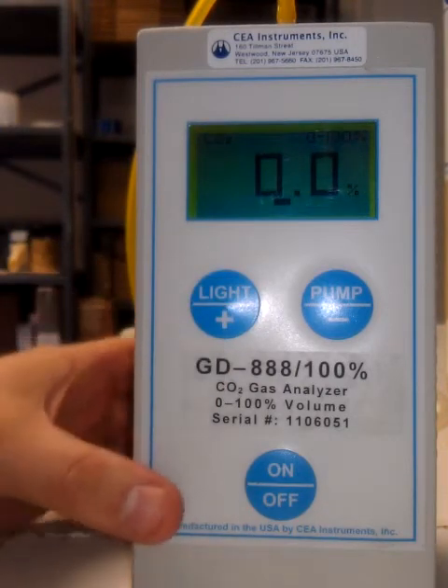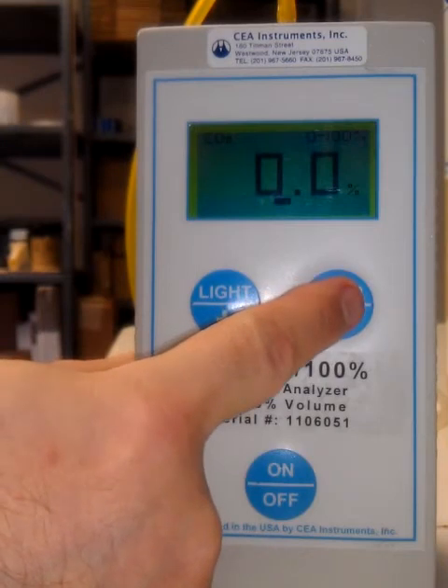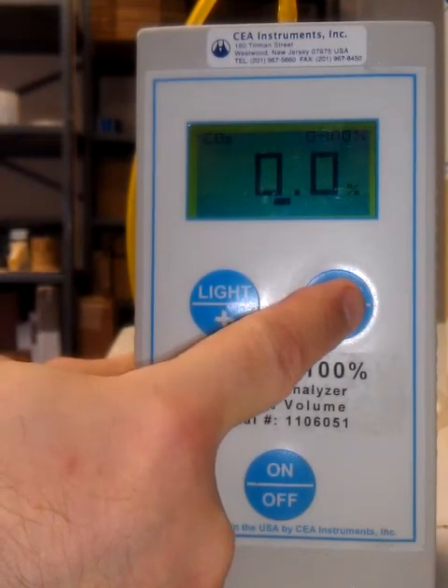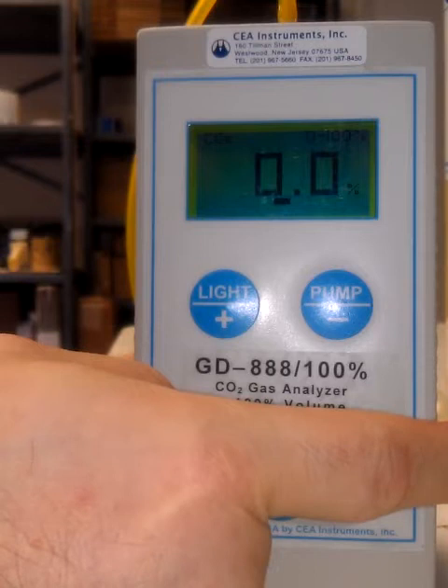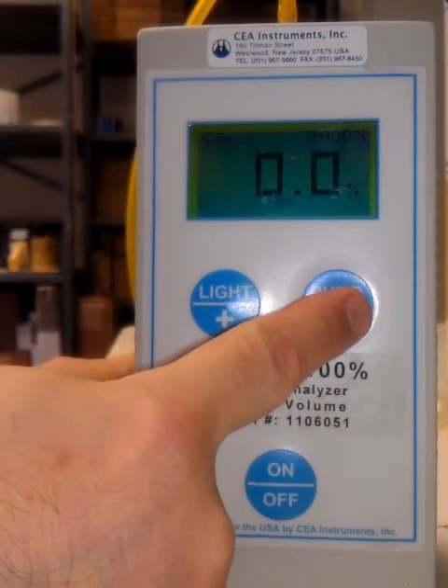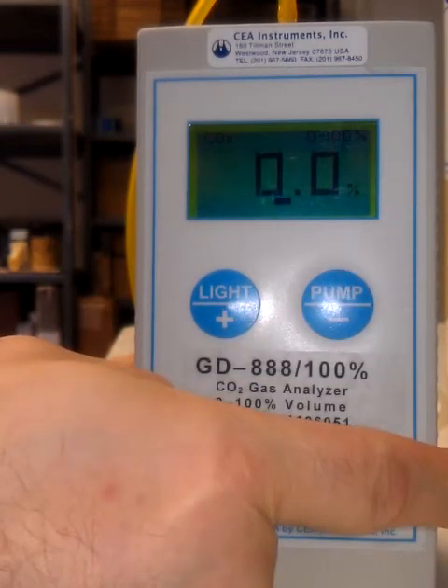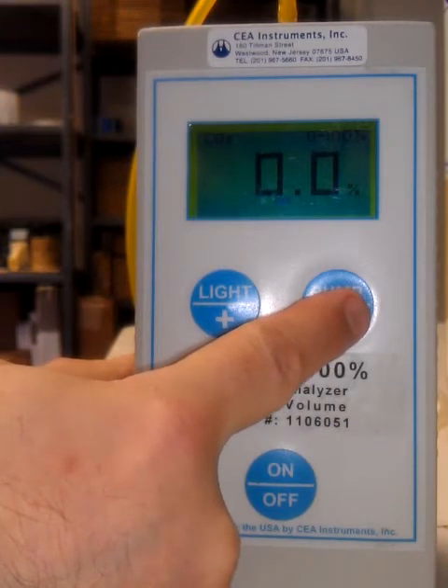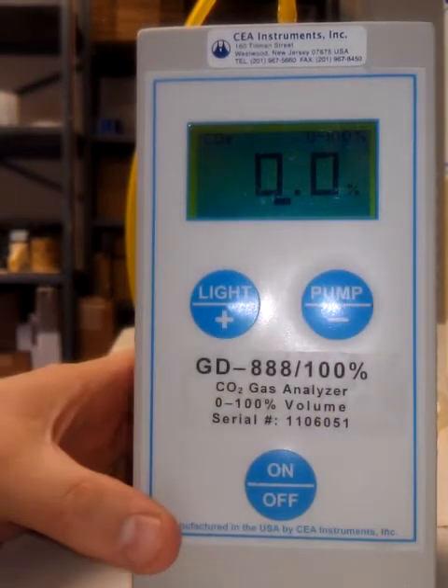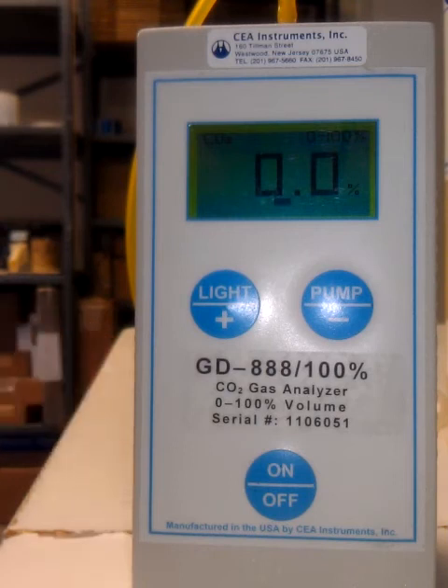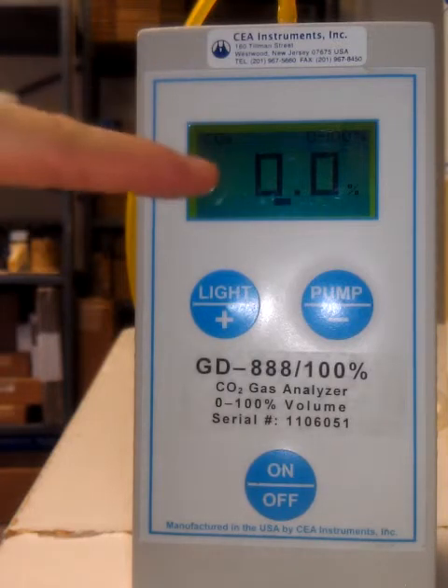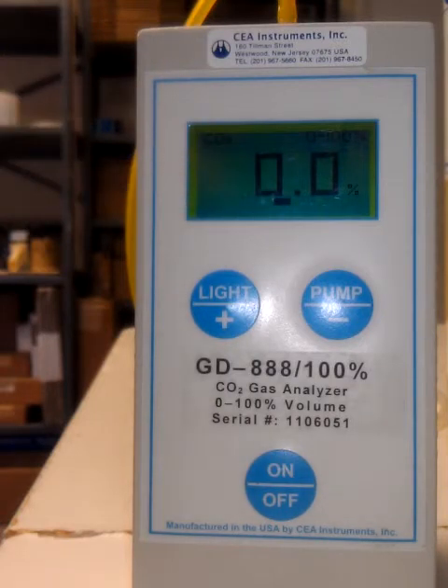The pump itself, you can turn on and off, same thing. You hold it, beep, and the pump is off. Beep, pump is running. While the pump is off, if you introduce a cylinder of the 99.9 or 99.99% carbon dioxide gas and the display does not go, then you should do a calibration. To perform a calibration, this is exactly what you must do.